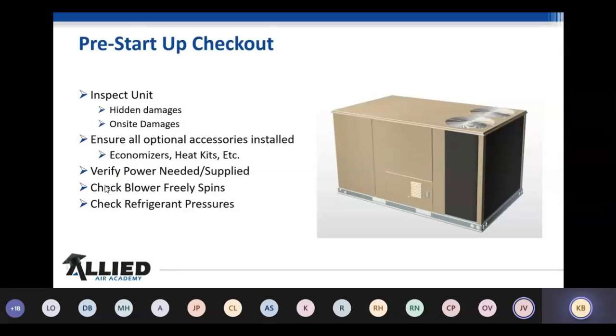So one of the first slides we got right here is inspect the unit for hidden damages and on-site damages. And if you look at the picture of this unit I've got right here, it actually has the black cardboard protecting the coil up front. That's one of the things I've always asked: you could put it back on while you're craning the thing up to the top, but check your coils and make sure that they're good to go, and all that good stuff.